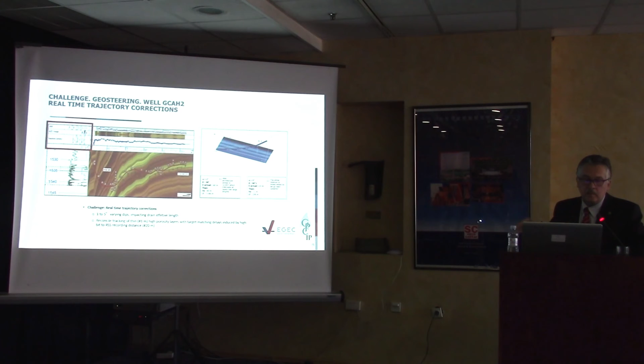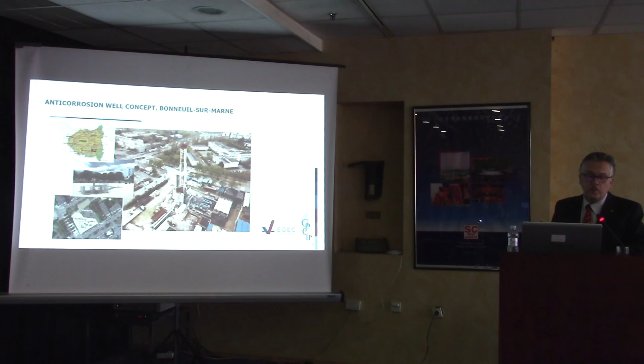It's on a site where, similarly, we had to renovate the existing installation because there was already a doublet in operation, consisting of a production well and an injection well. The production well was in quite bad shape, producing about 150 cubic meters an hour, and this was quite unsatisfactory because production had declined. The well was strongly damaged by corrosion and scaling, so the operator decided to have a new production well after a certain time.